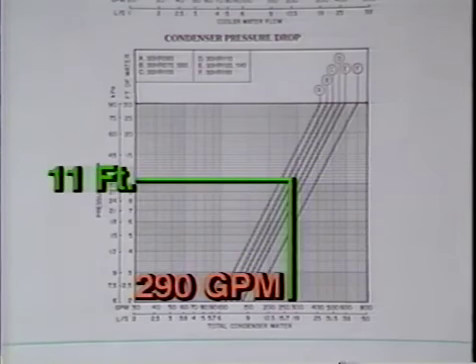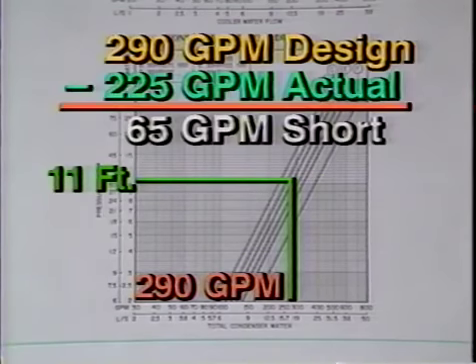Remember, our sample was 6.9 feet, which reads 225 GPM. Our sample is 65 GPM short. This would be an indication of low flow in the condenser and will have to be corrected so the chiller will run at its design capacity. We will discuss this in more detail later in the program.